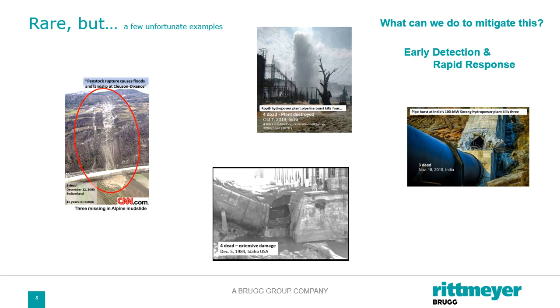Often people only look at above ground penstocks when they think about leak detection. You might think that if it's buried or in a tunnel, you've got the counter pressure of the ground around it to help minimize damage of a rupture, and there's certainly some truth to that. But if you look at these 4 examples, they were all buried tunnels. The one in Switzerland was actually 100 meters deep and worked its way up through fissures in the rock and through very thick steel pipe, making a geyser in that large inundation zone. So while perhaps safer, even underground penstocks and tunnels need to be considered in your safety plan.